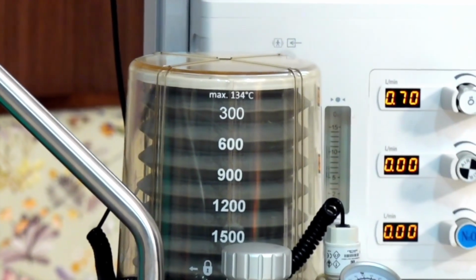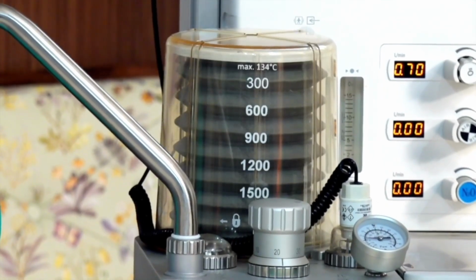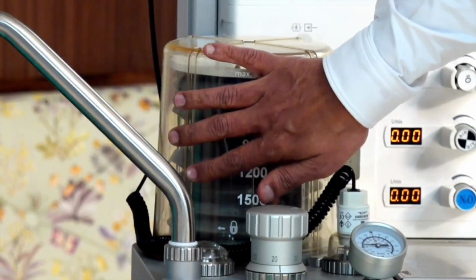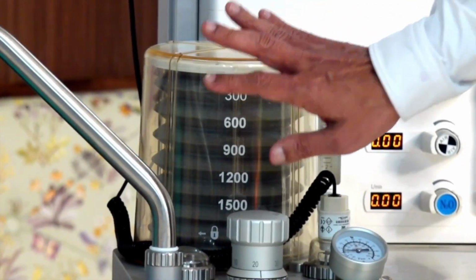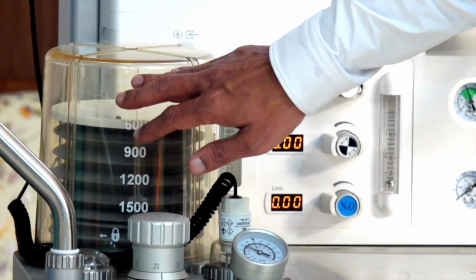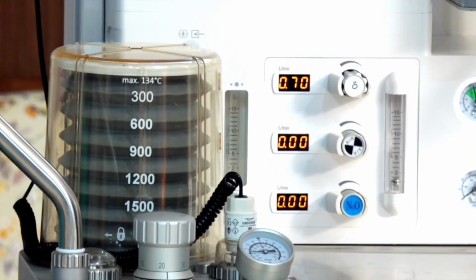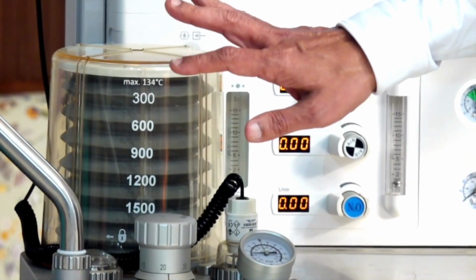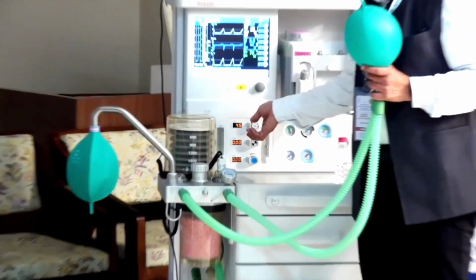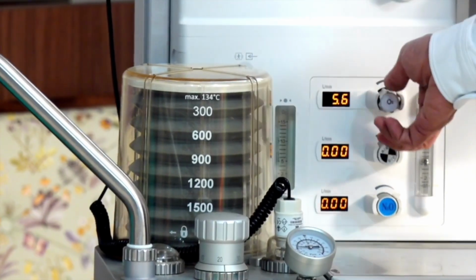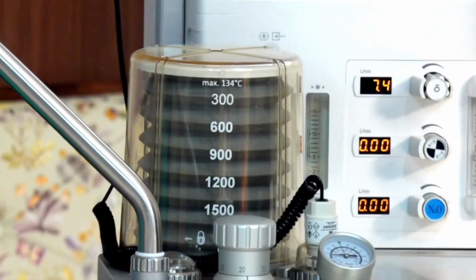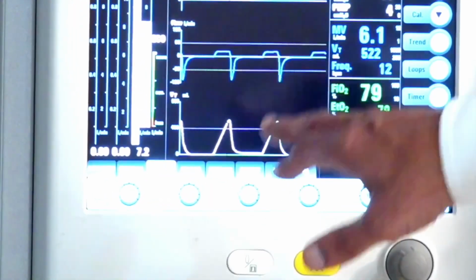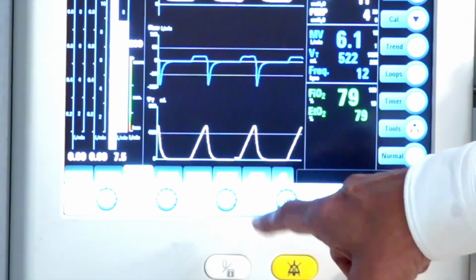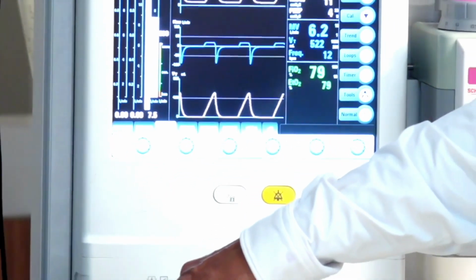The bellows movement depends upon the flow which you are setting, and this value is absolutely not relevant. So don't use this value to identify how much tidal volume is given. It is part of a standard requirement, so they are writing it, but it is not useful. If you increase the flow, it will change immediately. It will start showing low. So even if we are targeting 500 tidal volume, it will not show 500 because the machine is giving less now. To keep this at 500, when I am increasing the flow, it is reducing the bellows movement.